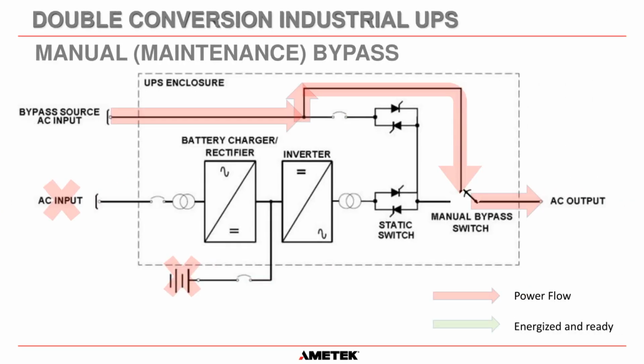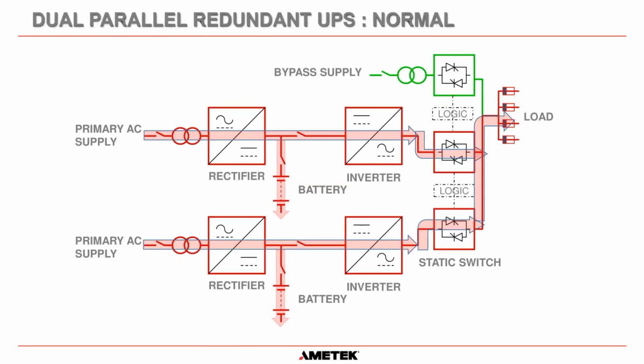And then the last thing we have is the manual bypass switch, and that allows us to bypass power around the static switch. You can see that this contact here has moved to this position, and that allows us to remove power from here, and if it's an external remote manual bypass switch, it actually allows us to remove power, and it would go outside of the UPS that way there. But it makes the UPS safe to have maintenance or repairs done on it. Okay, so that's the general theme, the basics of how a UPS works.